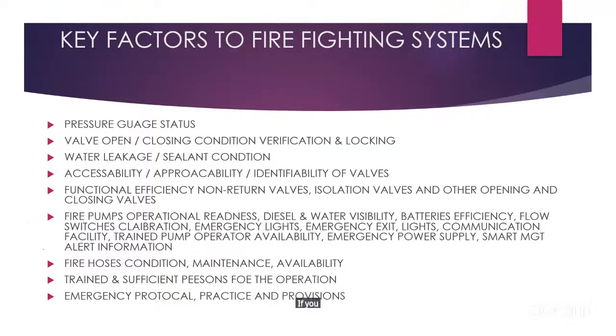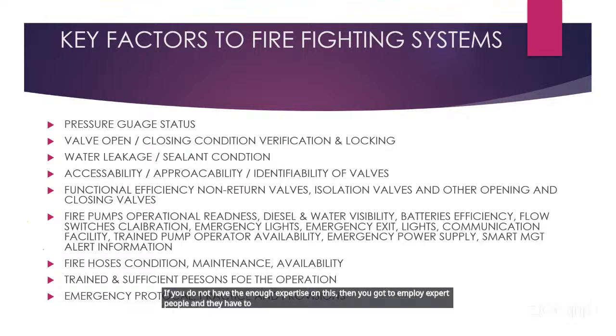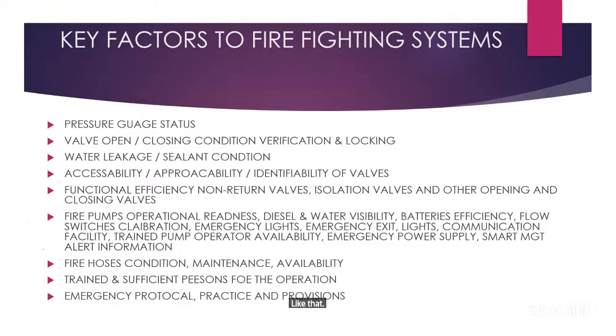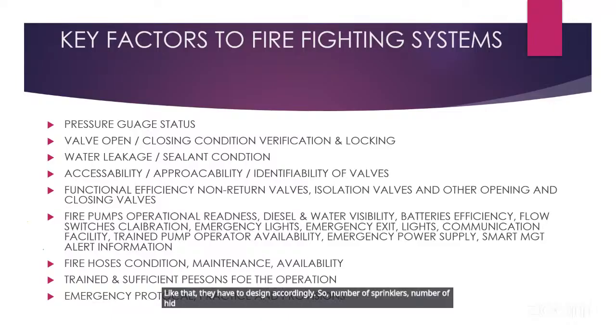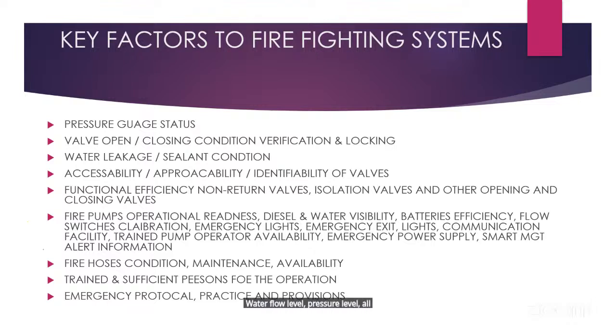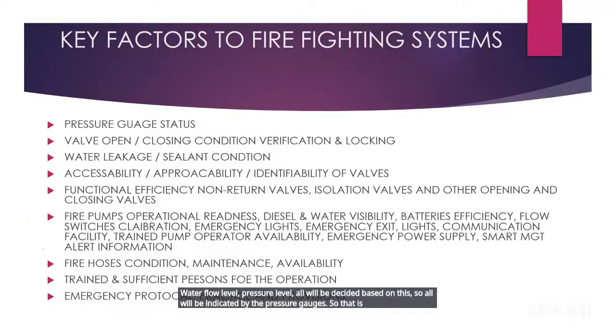If you do not have enough expertise on this, then you have to employ expert people, and they have to do this calculation, and decide what fire pump capacity you should have, what should be the maximum pressure, and what should be the minimum pressure. They have to design accordingly. So the number of sprinklers, hydrants, and hard hydrants should be decided based on your actual risk requirement. Based on that, hydraulic calculation will be done, and the water storage level, water flow level, and pressure level will all be decided. All will be indicated by the pressure gauges. So that is a very important item that you should look into.